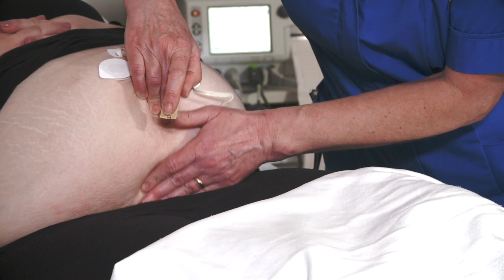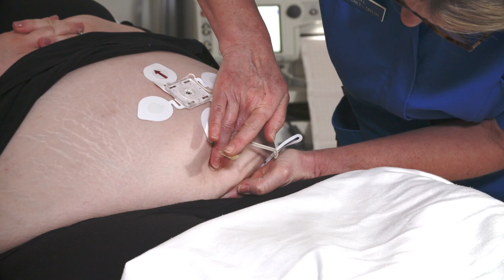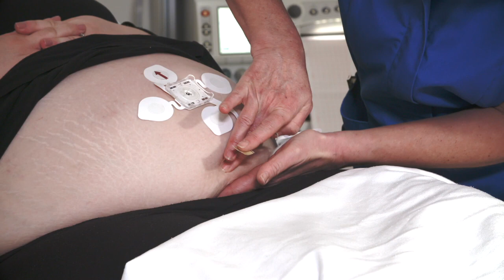Now for the last bottom electrode attached to the long, flexible cable. This electrode center should be placed on the midline 6 cm above the rim of the symphysis pubis. This is the width of 3 or 4 fingers. You may want to consider using gloves anytime the pubic area is being palpated. As with the other electrodes, check where this electrode will be placed, avoiding skin lesions and skin folds.